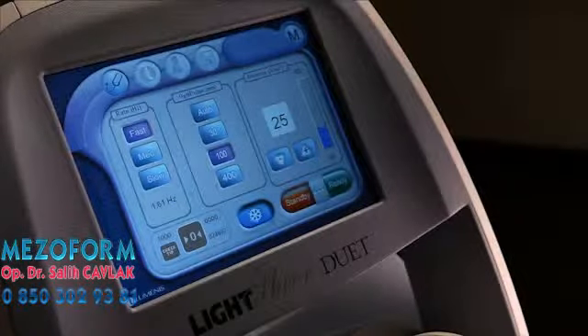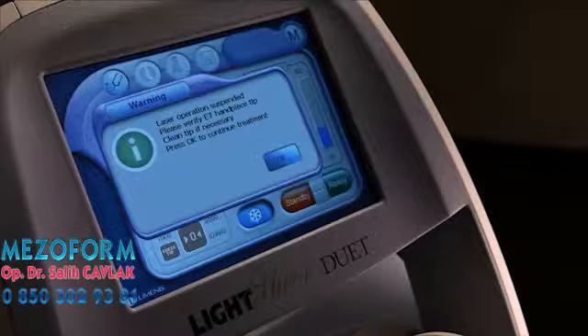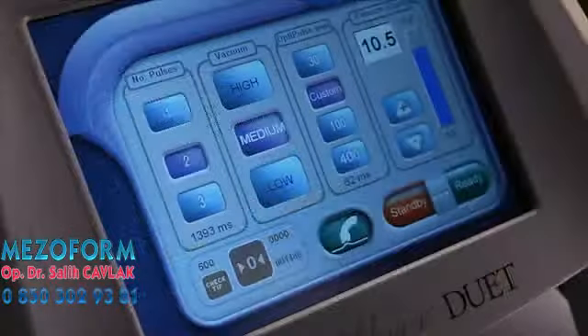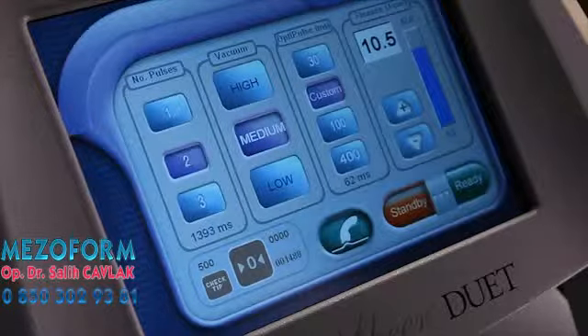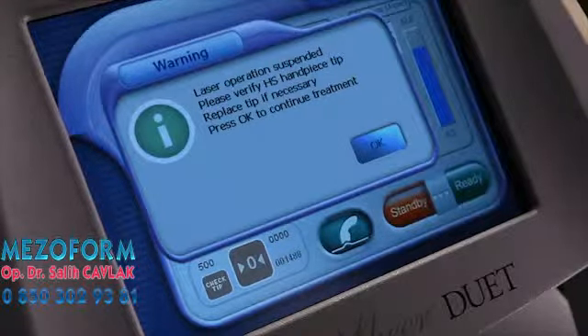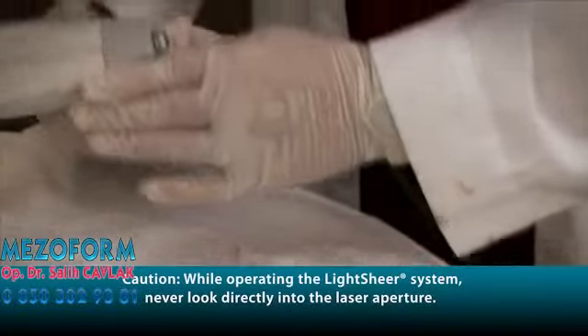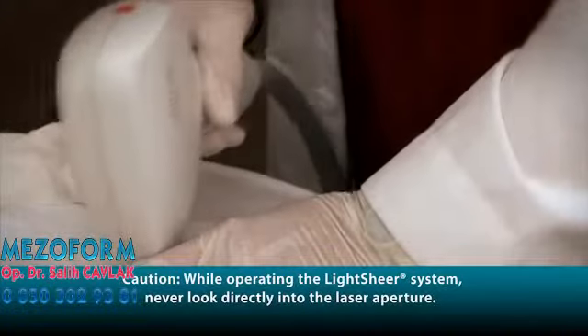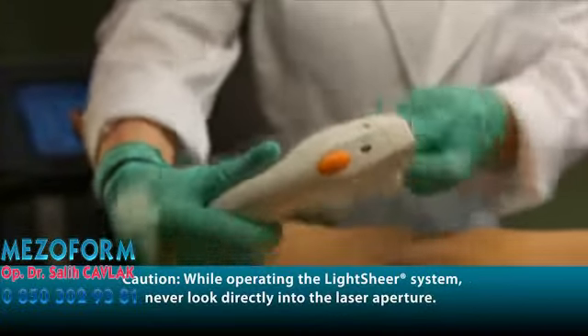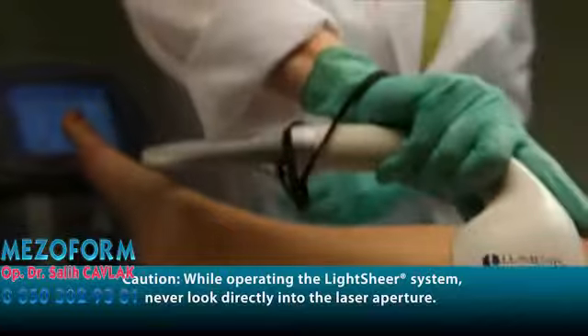The ET handpiece tip counter will produce a cleaning reminder message after 1,000 pulses. The HS handpiece tip counter will produce a cleaning reminder message after 500 pulses. However, each handpiece tip or insert should be observed and cleaned frequently throughout treatment to verify patient safety and prevent equipment damage.